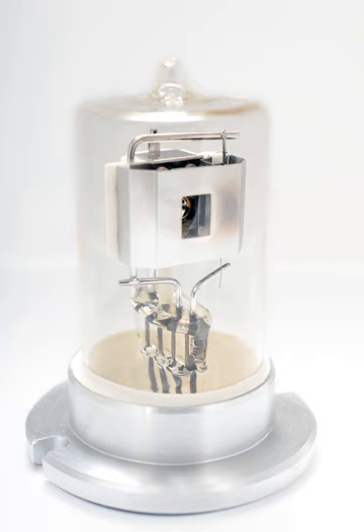Unlike an incandescent bulb, the filament is not the source of light in deuterium lamps. Instead an arc is created from the filament to the anode, a similar process to arc lamps.